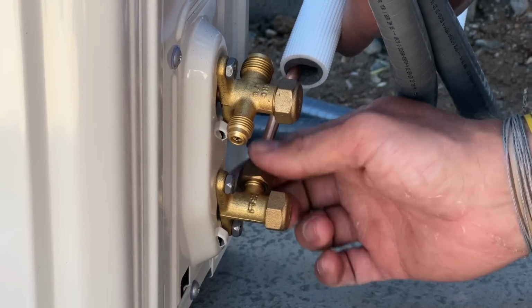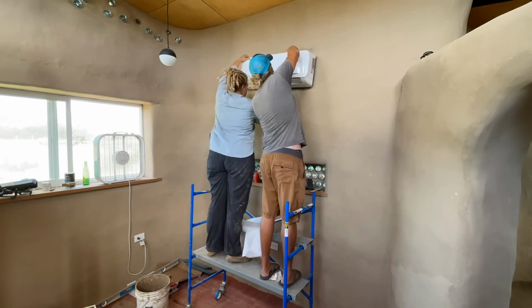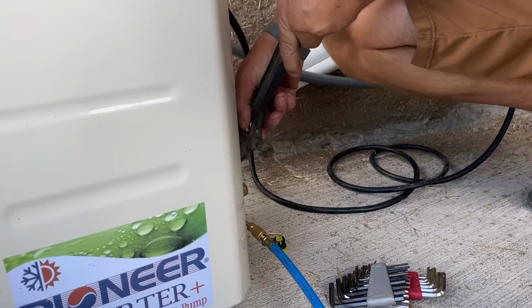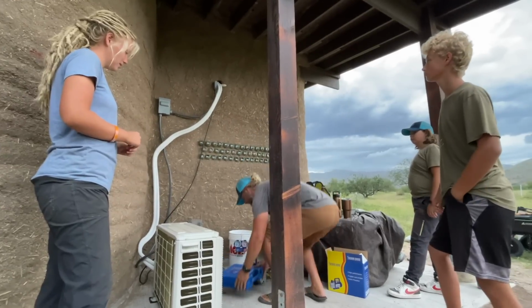Funny story: the first mini split we installed over on the solar shed, we pulled all the stuff through the wall, connected the gas lines, and then said, let's move the outside unit where it needs to go. As soon as we moved it, it broke that seal and refrigerant started rushing out. We had to turn it all off, recut the lines, reflare them, the whole thing. Thankfully it was okay, but refrigerant is so expensive, so you don't want that to happen. You don't want a leak.